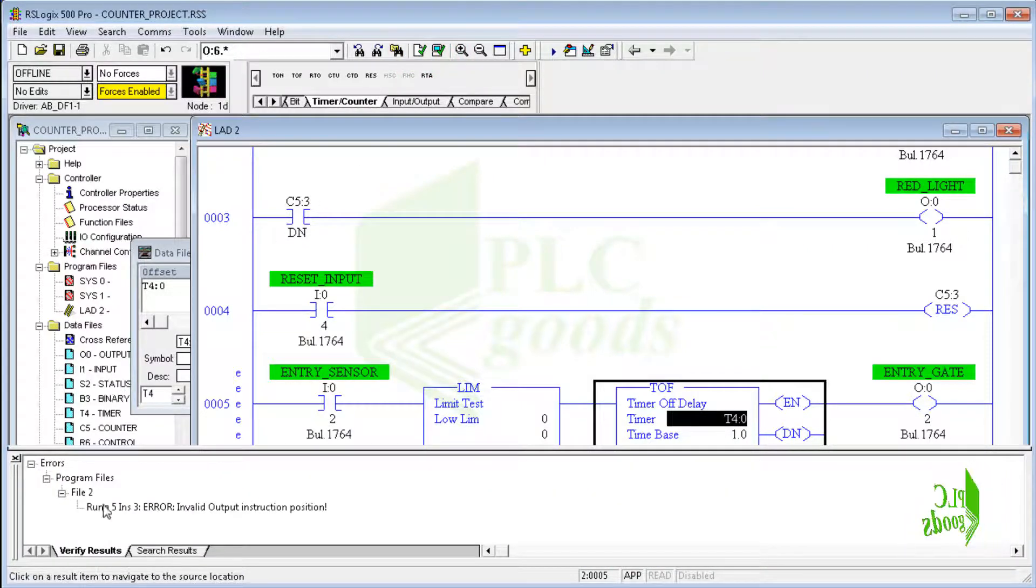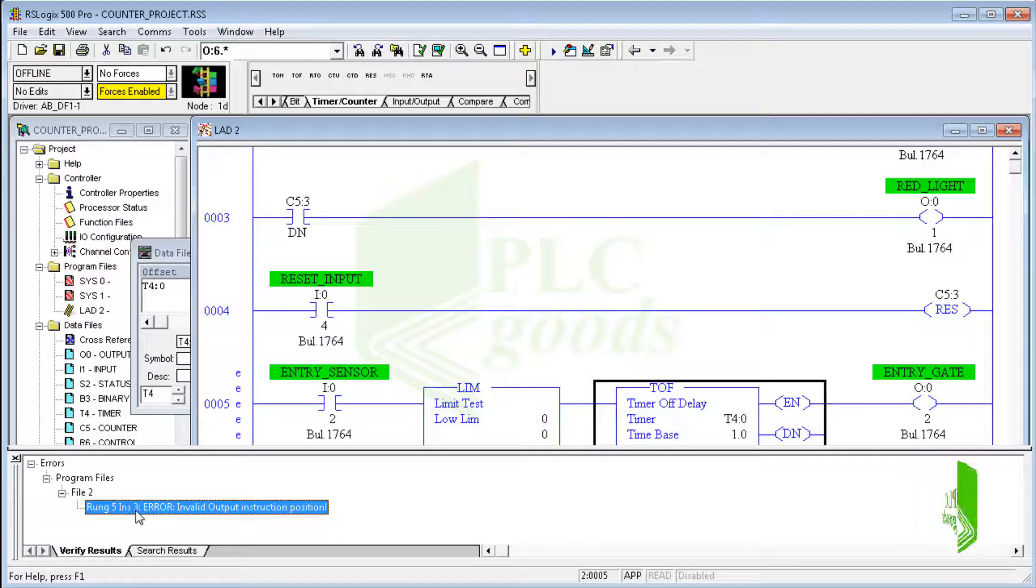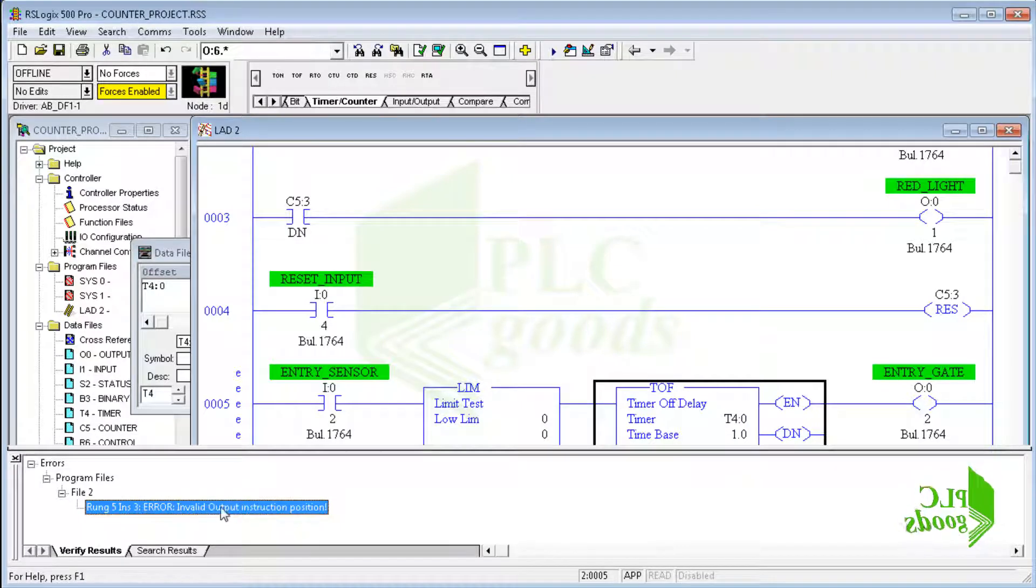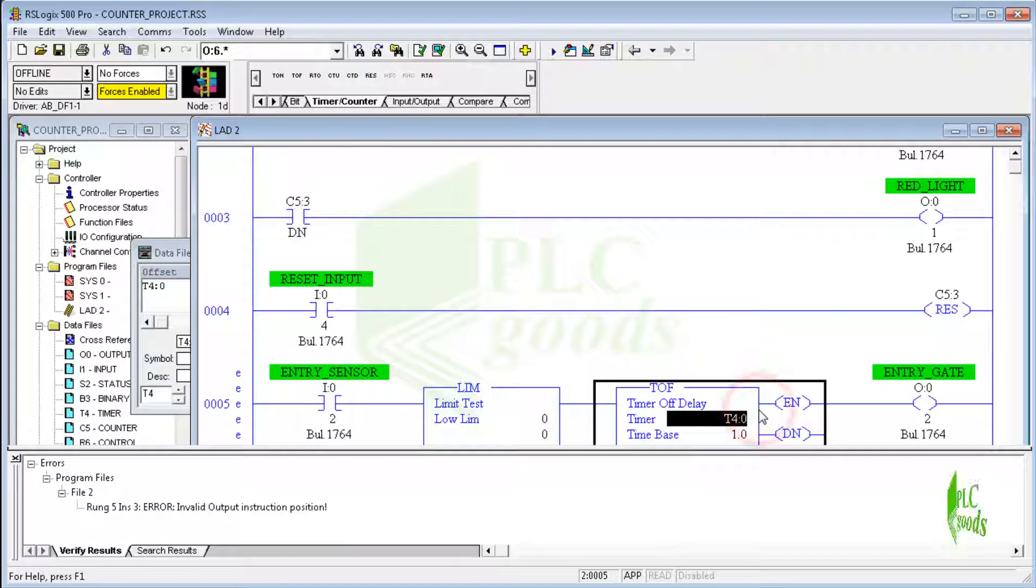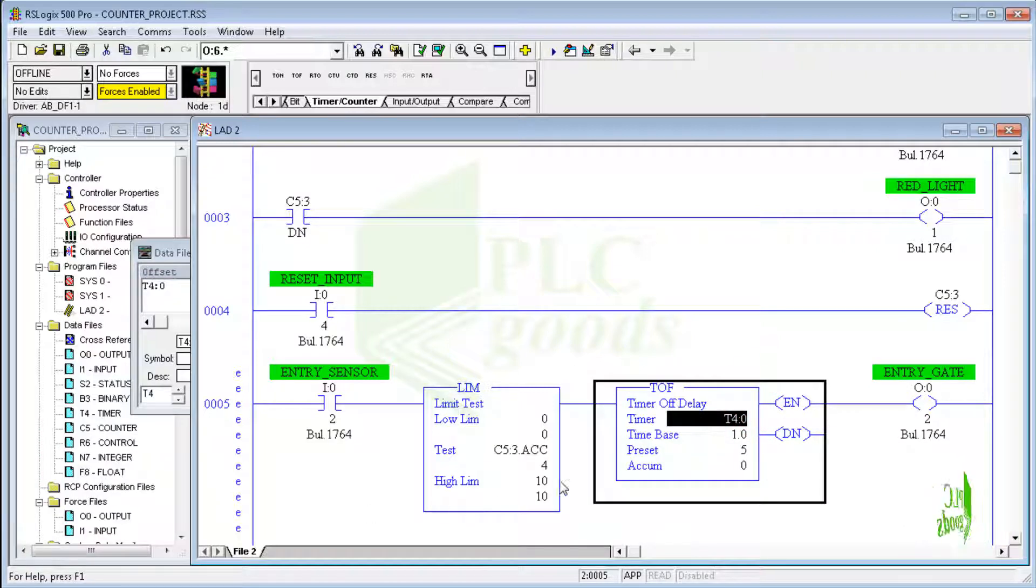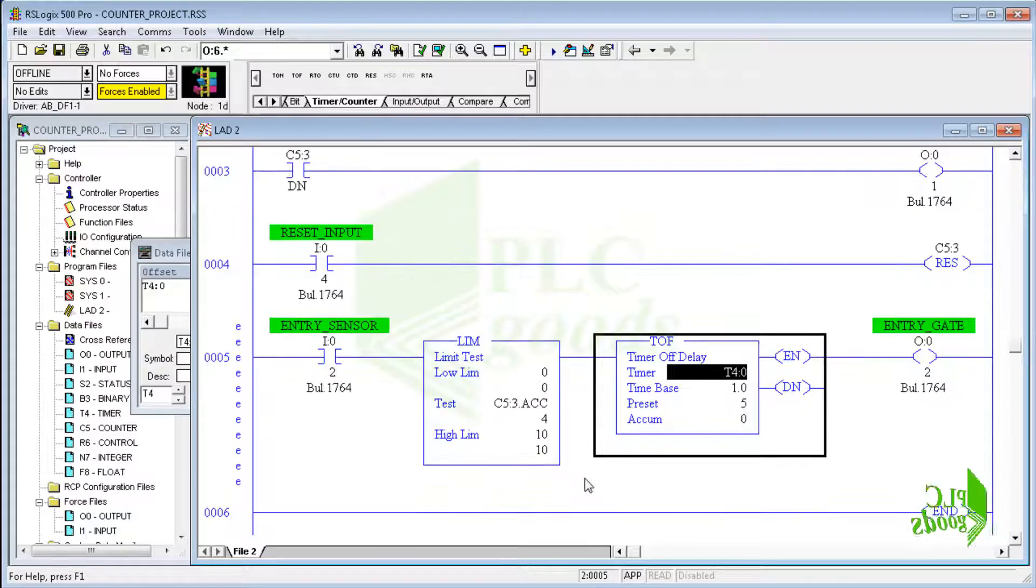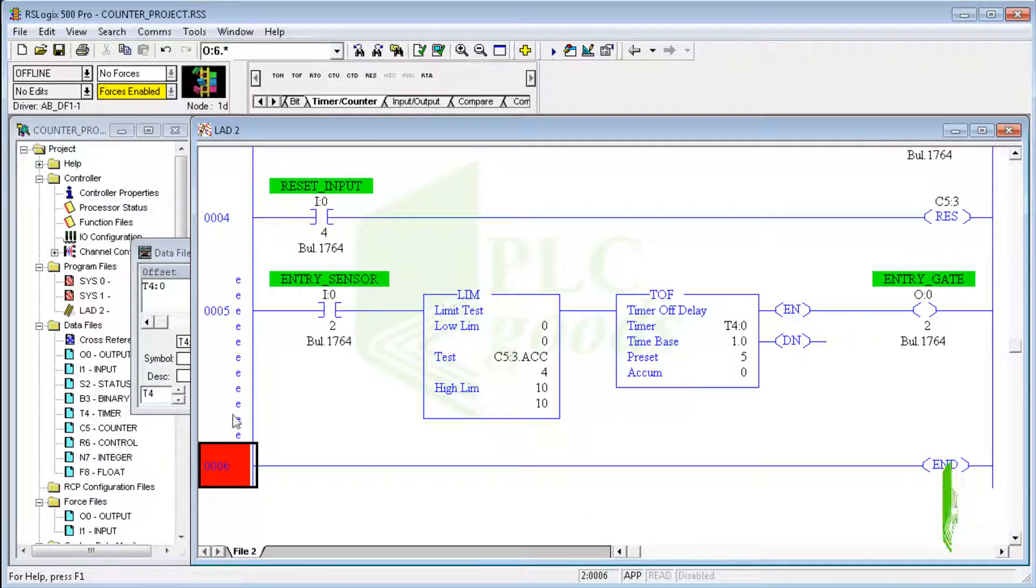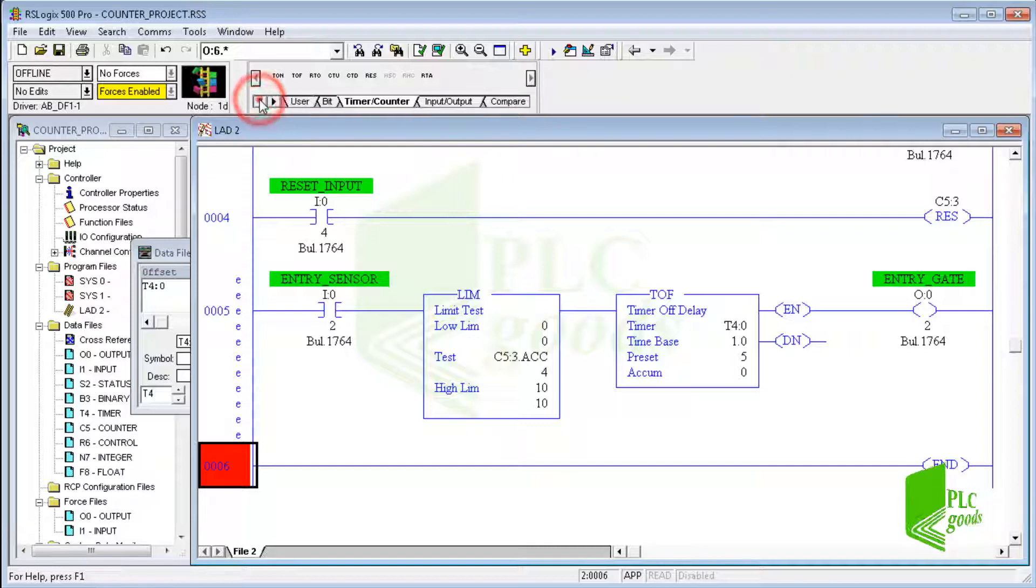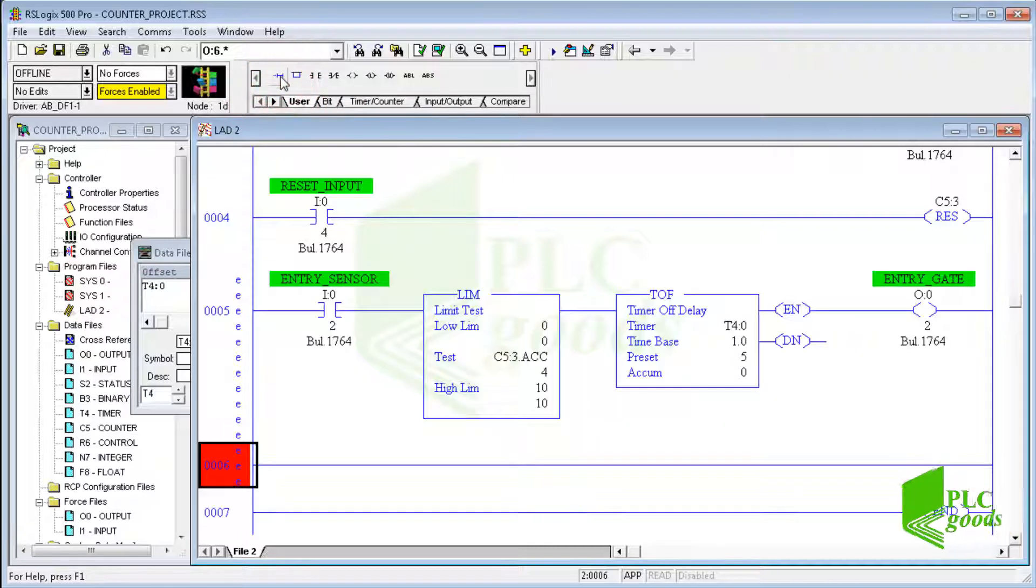Let me compile the program. Well, here is an error. This message, invalid output instruction position, is on rung 5 for the third instruction. To solve this error, I have to use the output and the off-delay timer in two lines. So let me use the output instruction in the next line and use the done bit to turn on the entry gate.